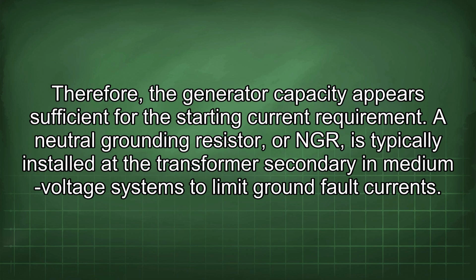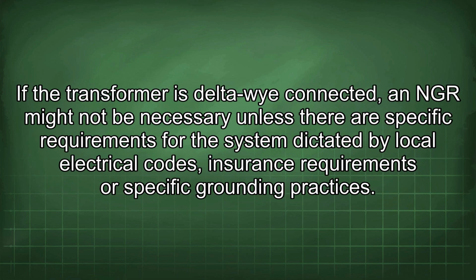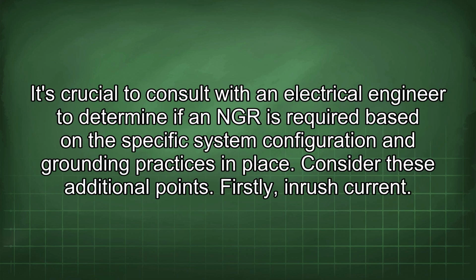A neutral grounding resistor, or NGR, is typically installed at the transformer secondary in medium voltage systems to limit ground fault currents. If the transformer is delta-Y connected, an NGR might not be necessary unless there are specific requirements for the system dictated by local electrical codes, insurance requirements, or specific grounding practices. It's crucial to consult with an electrical engineer to determine if an NGR is required based on the specific system configuration and grounding practices in place.